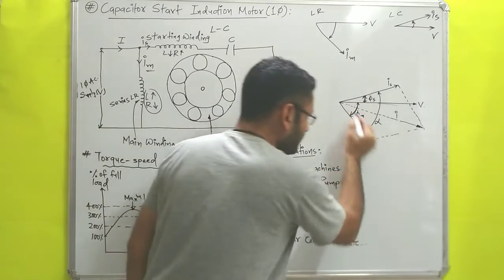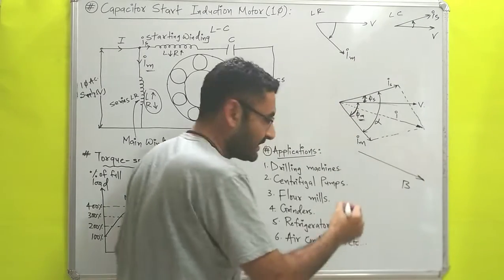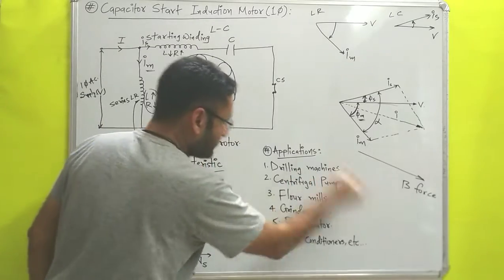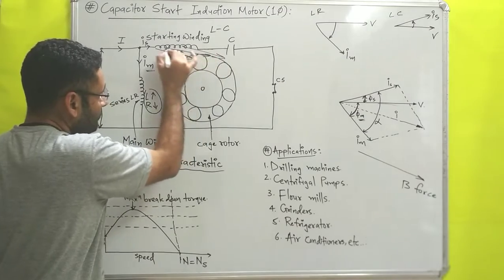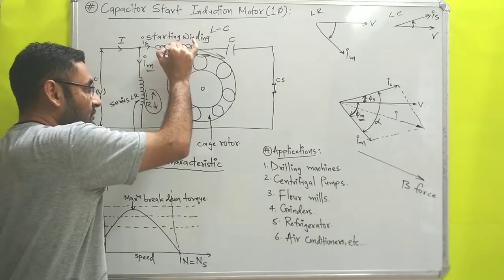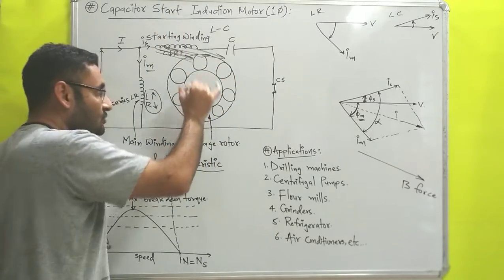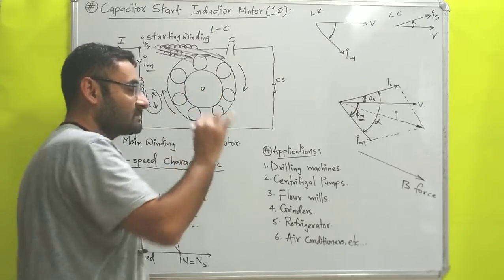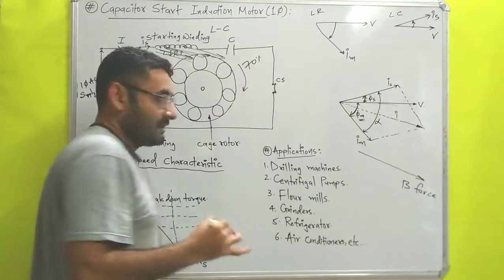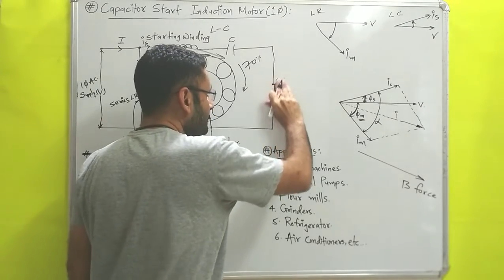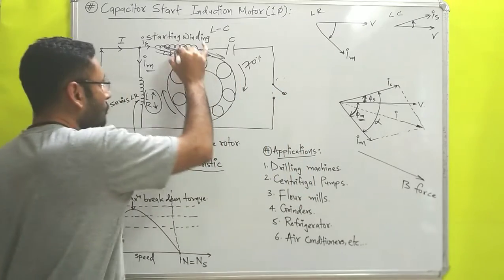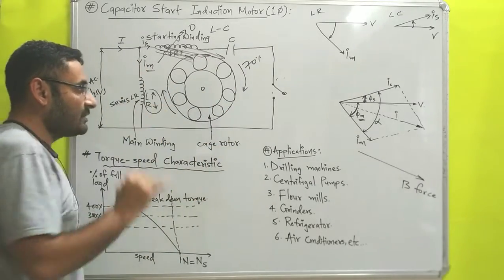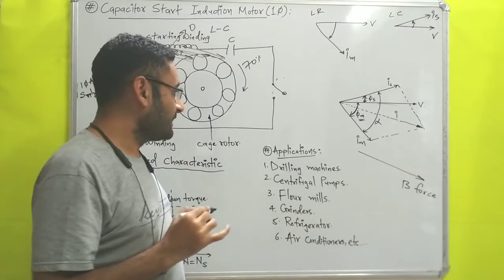Due to the resultant current, a magnetic field is produced according to Faraday's principle. That magnetic field produces a magnetic force in a specific direction, which is imparted on the rotor. Due to that force, the rotor gets an initial torque and starts to rotate. When the rotor speed reaches 70% of its normal speed, the centrifugal switch opens, so no current flows from the starting winding, and the rotor continues rotating with only the main winding.